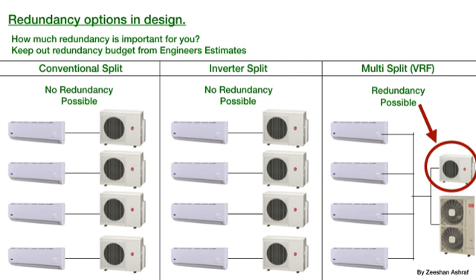The capacity drop table per feet length and the pipe limit charts of manufacturers are available in the manufacturer's manual. Please search the same on the internet. Other problems are hot air and facade, which cause extra load. It is unfortunate that when you install a single split, you have no redundancy options. So in case of VRF, it is better to keep the redundancy budget separate.